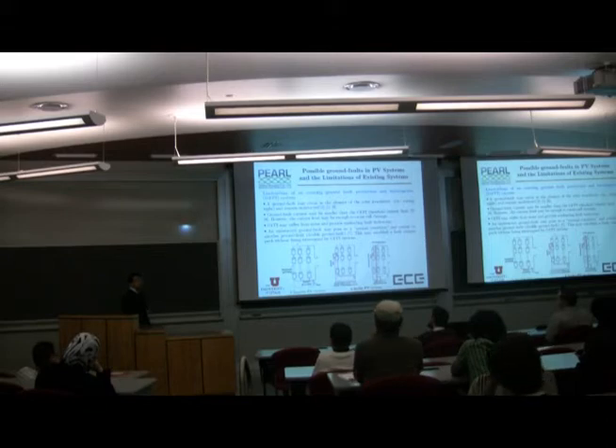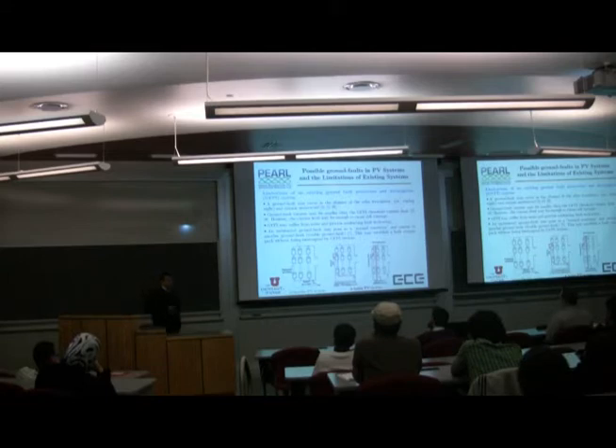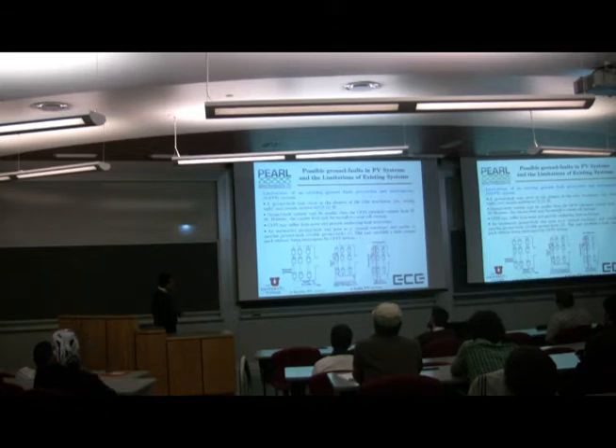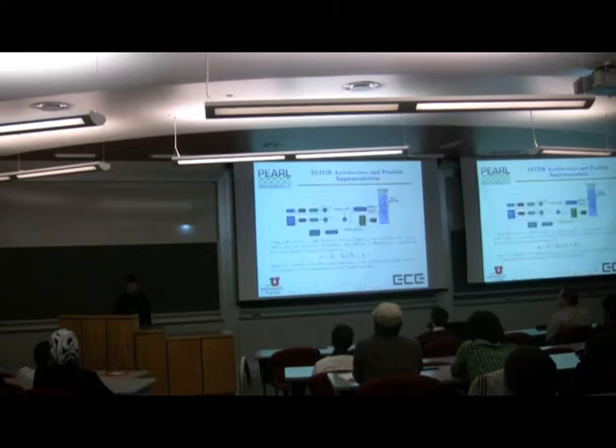So what will happen is it will not trip the system immediately, but in the morning, when you have some slight current, you will have the short circuit current circulating in the panel, and it would actually cause damage. This is actually showing how damage is caused: there is an internal short circuit between one of these terminals and the chassis. Heat is generated in that localized string of cells, and that can cause a secondary or tertiary fault, which means the fault propagates and causes multiple faults in the system.